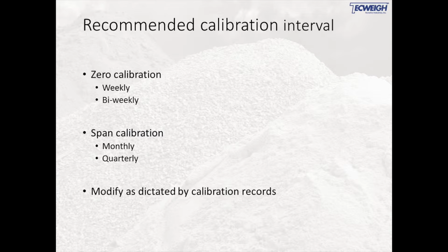I would recommend calibrating whenever the scale is no longer reading 0 when it's supposed to be 0, and if you have any doubts about the span calibration, you can always check those and run them on more of a regular basis. With built-in test weights, it makes running a span check very quick and easy.